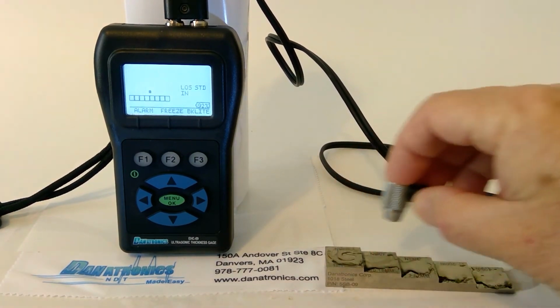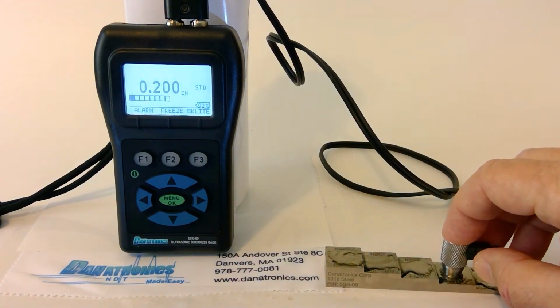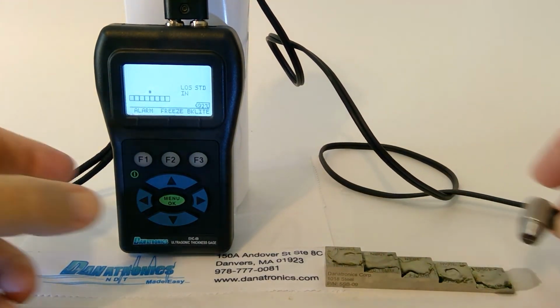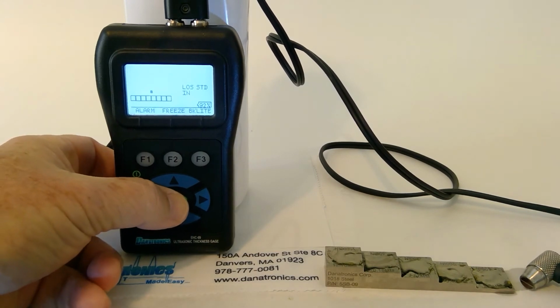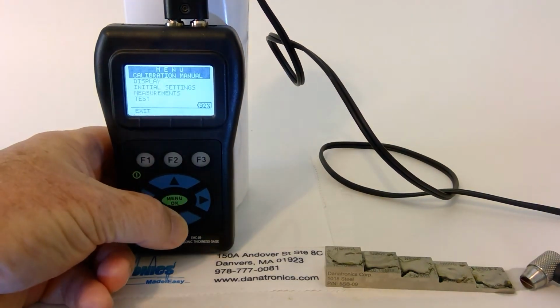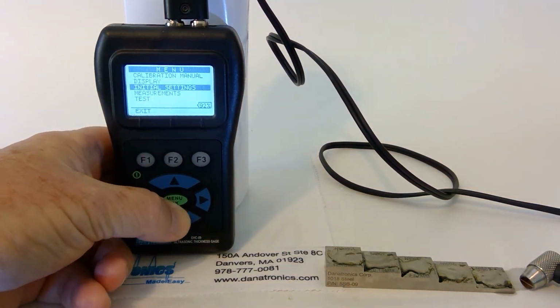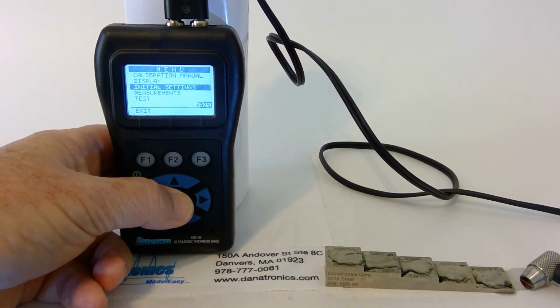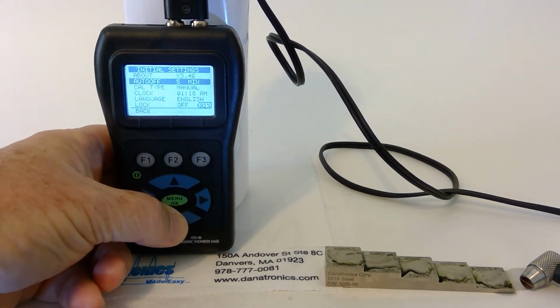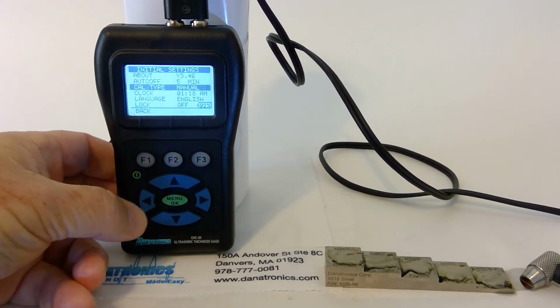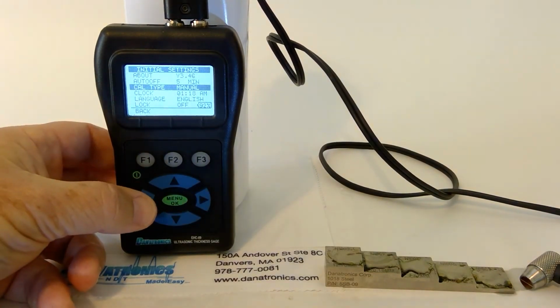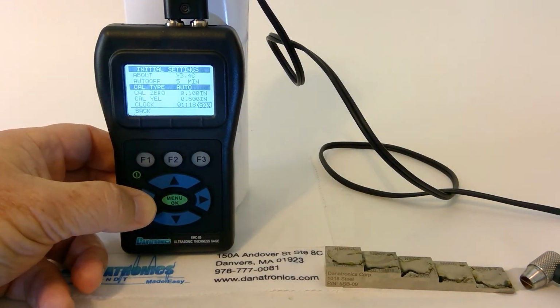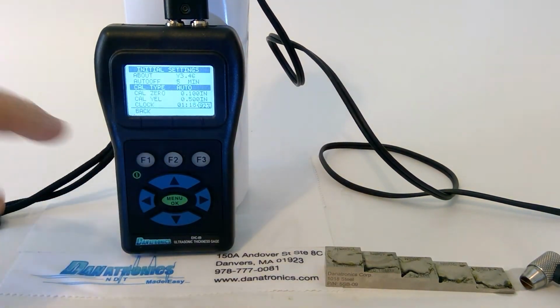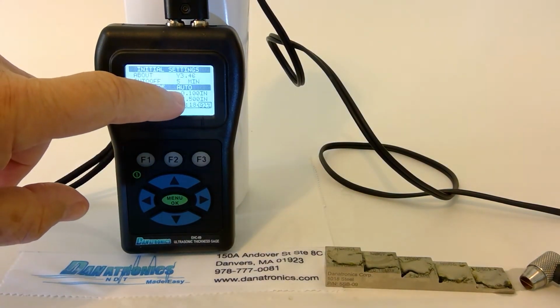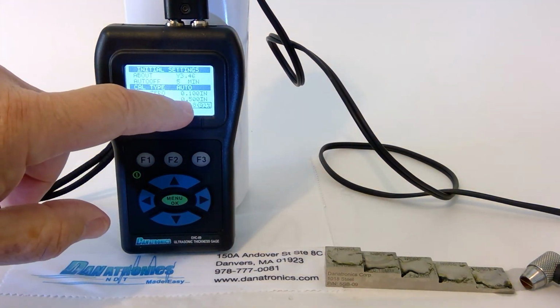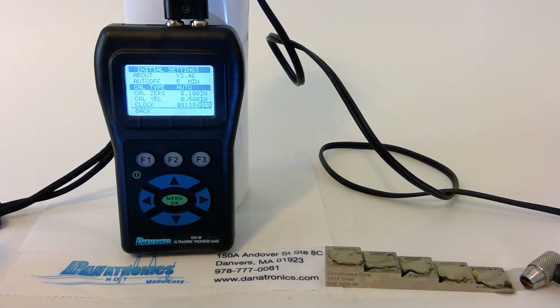To perform the auto calibration function, we press the menu, slide down to Initial Settings, slide to Cal Type, and with your left or right arrow button, change it to Auto Cal. You will notice the two readings, 100 thousandths and 500 thousandths, correspond to the block we are using.